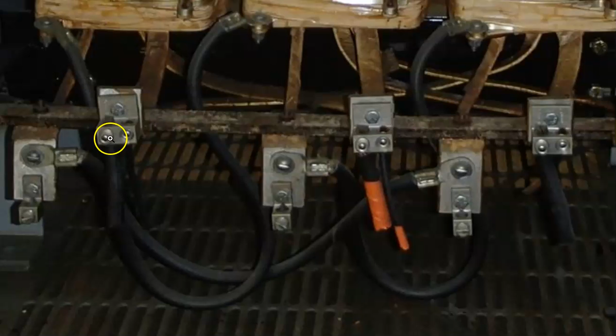The rest of these over here are simply parts of the transformer winding. It's a flat type of winding that has been taken and bent out and pushed back in, and then wrapped around and bent out and pushed back in, and they provide connection points. The way that these taps are changed is that you obviously have to take power down and lock out, tag out. Then you pick the correct tap. They should have identifiers on them. There's usually just a transformer legend.